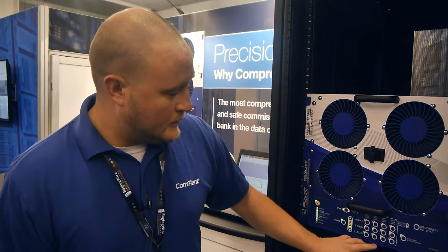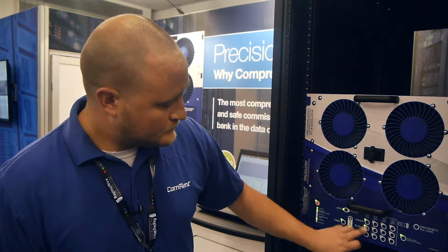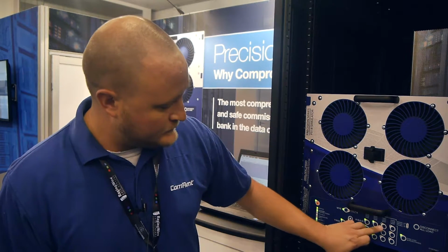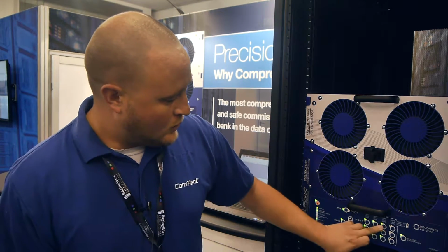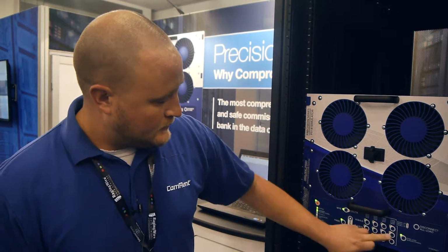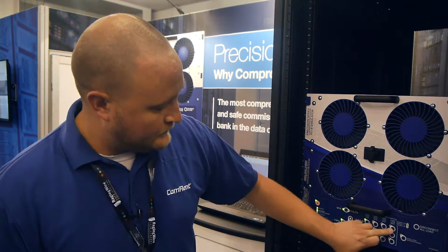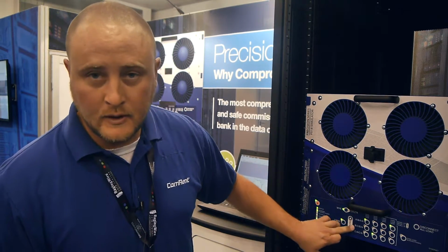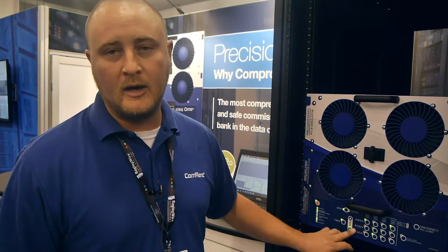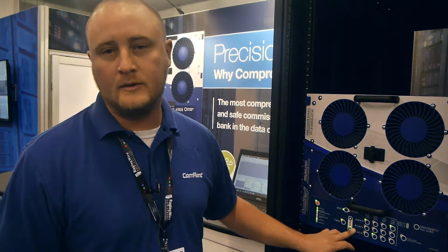The other ability here is that we can sync load, so the system acts as a three-phase and applies load in sync, or we can remove load and apply it in a single-phase manner, applying load to the various phases. So we have the ability to unbalance phases, and the ability to load with balanced phases.